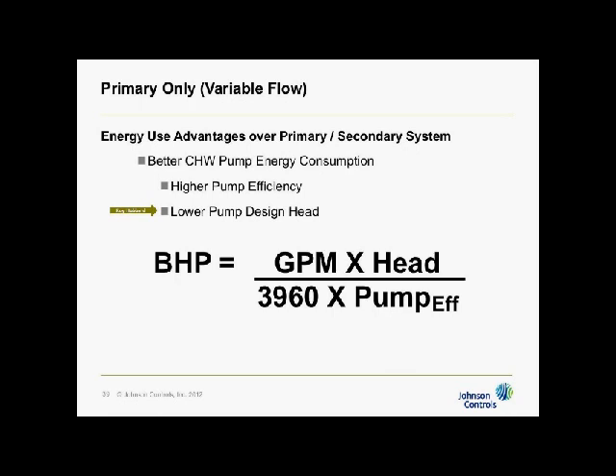When we were looking at primary secondary, the system we looked at, we had 40 feet of head in the primary, and we had 115 feet in the secondary, 15 of which was because of the secondary pumps being there. They have headers, they have valves, they have pumps. There is also head loss there that no longer exists when we're in a VPF system. So a similarly designed VPF system will have 140 feet versus the 155 in a primary secondary.